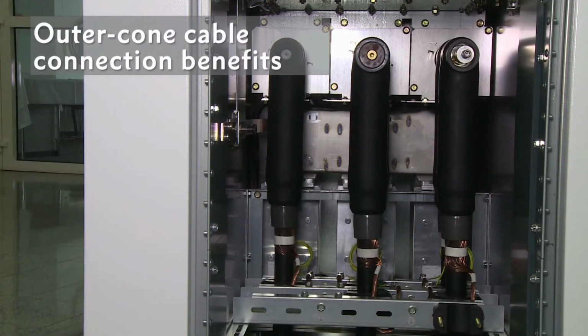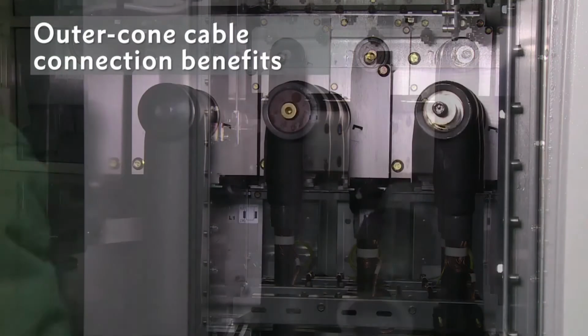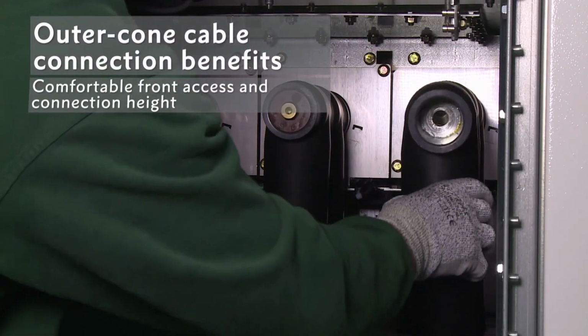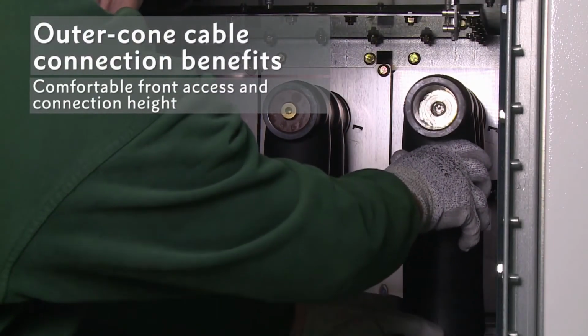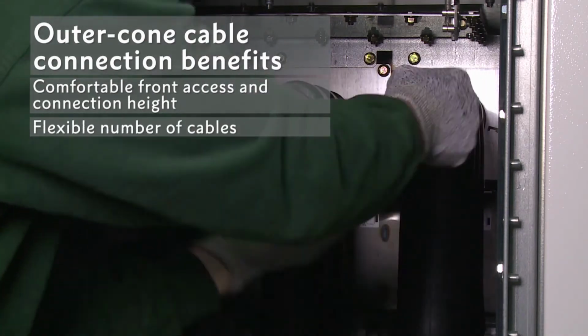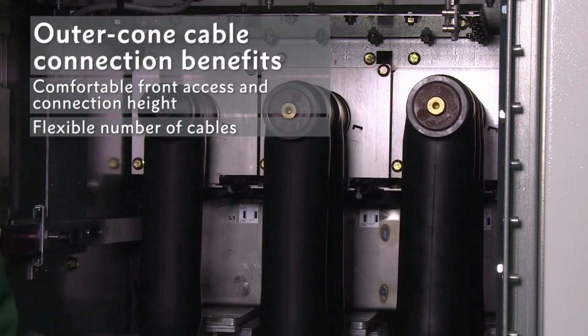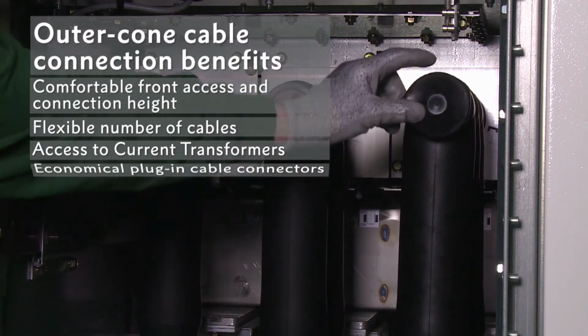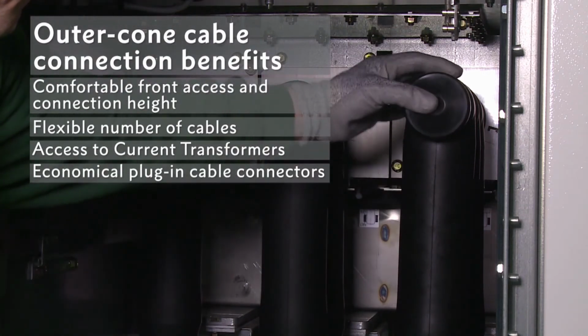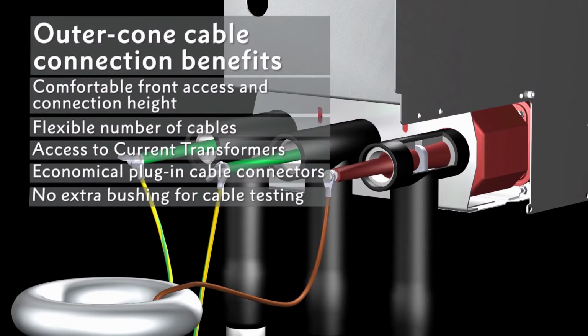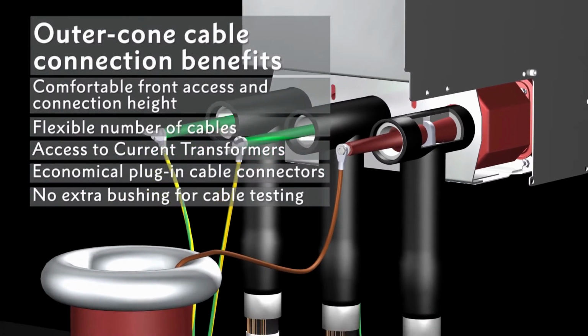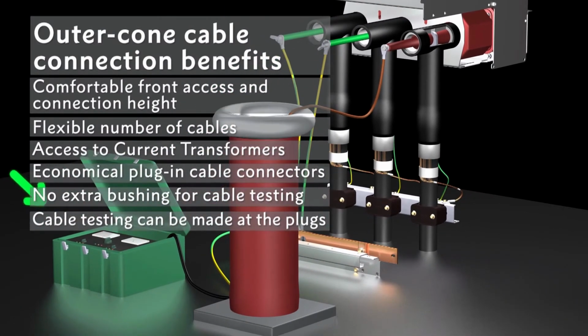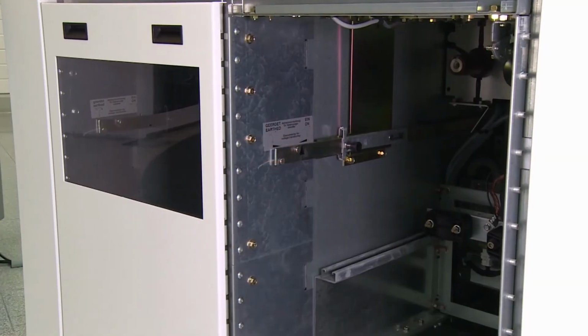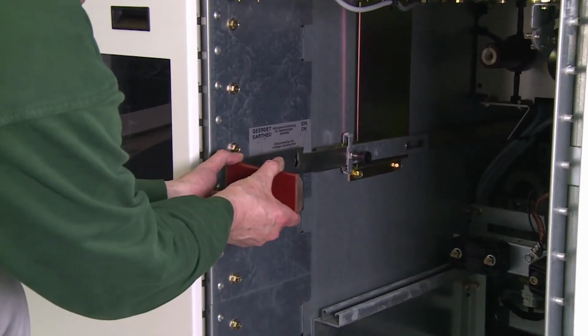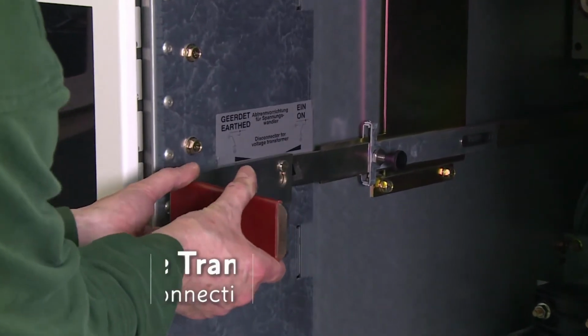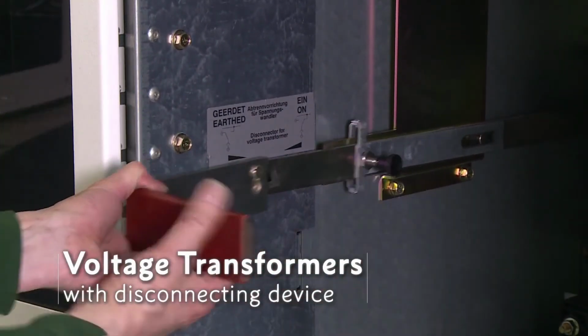Outer cone cable connection is recommended and offers numerous benefits, including comfortable front access for easy and safe cable installation, flexibility in terms of the number of cable connections, access to current transformers, more economical plug-in cable connectors. Plus, no extra bushing is necessary for cable testing, since cables can be tested at the plugs. For high-voltage cable testing or primary injection purposes, an existing voltage transformer can be disconnected and earthed.